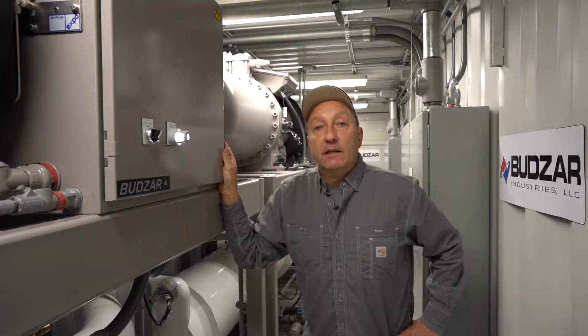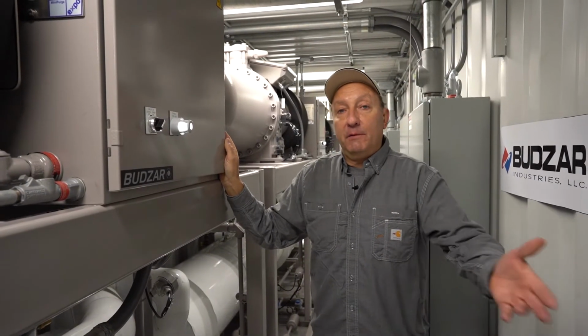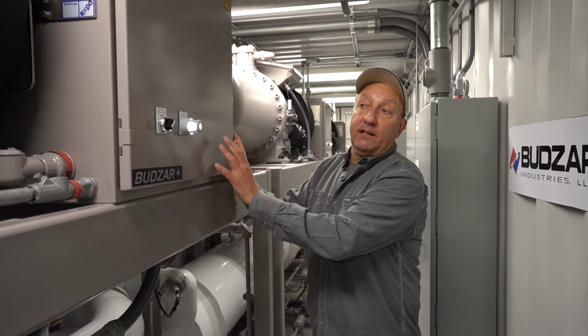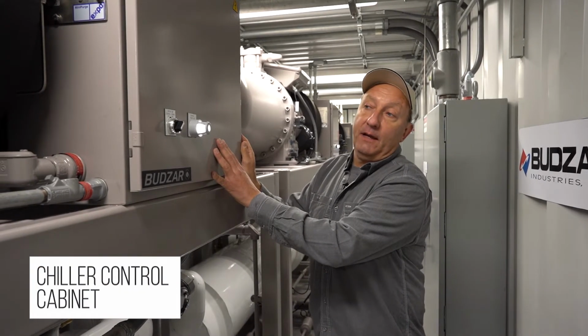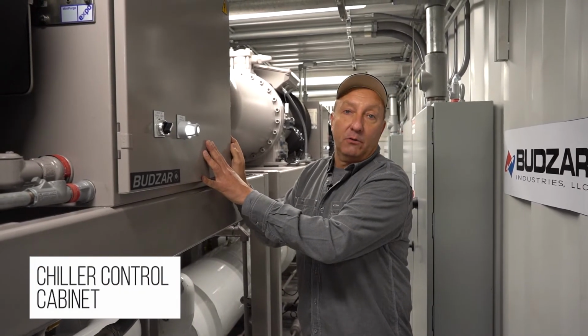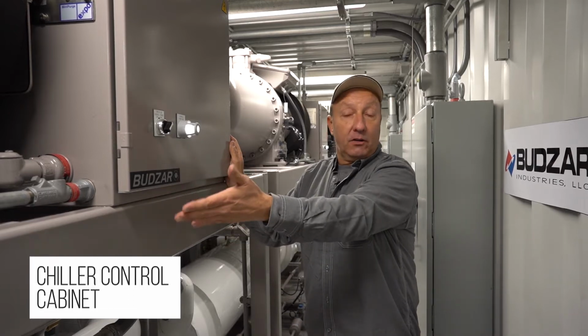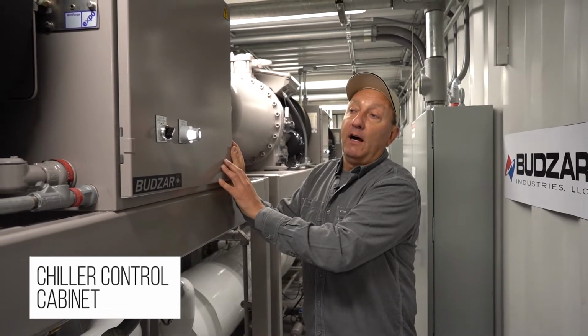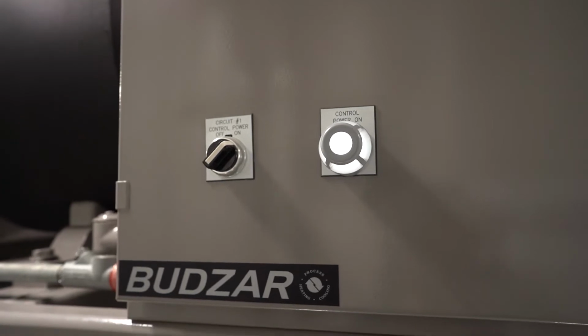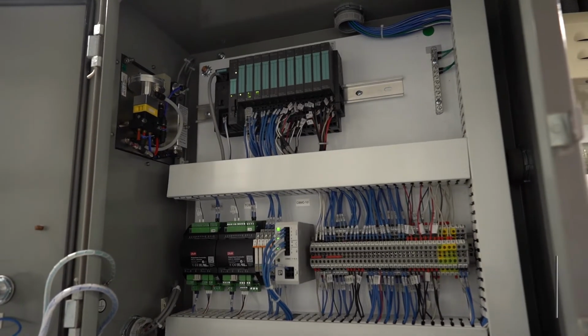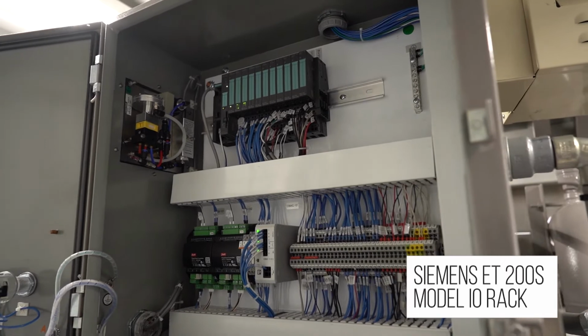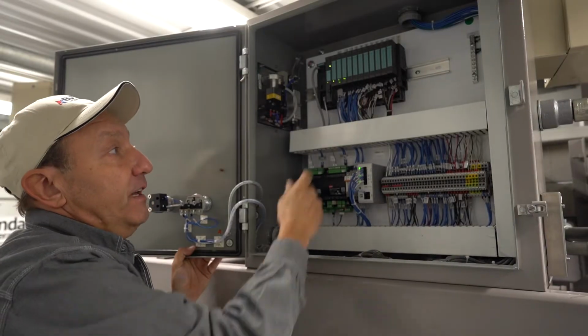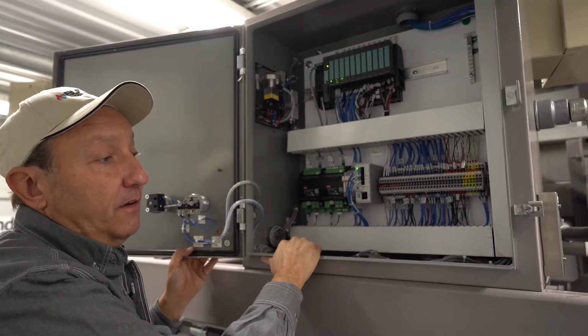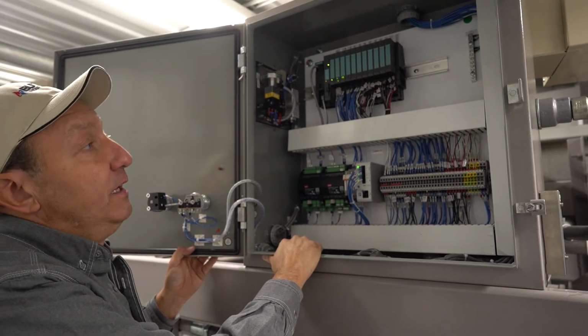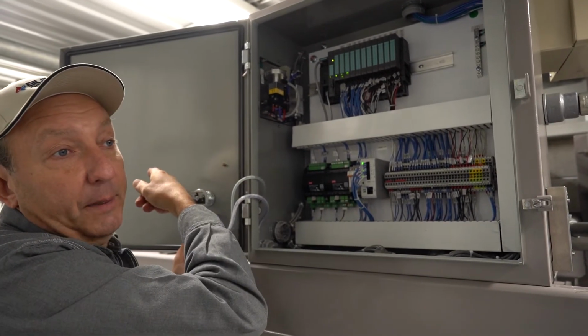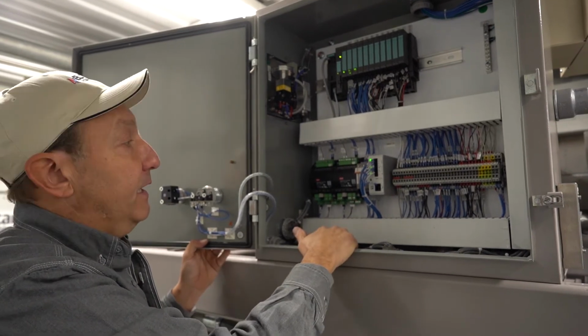Each chiller has a high voltage cabinet, which we already covered, but that also has a control cabinet. Inside this cabinet is the PLC I/O rack, which communicates with the main enclosure, which we covered earlier. It has its own power switch and power indicating light. Each control panel has a Siemens ET200S model I/O rack. This has all our inputs and outputs and all of our temperature and pressure sensors. These all go back to the main control panel where the HMI is located.